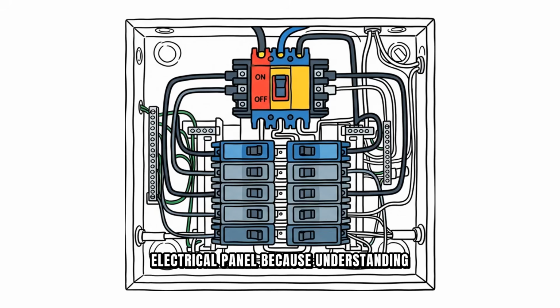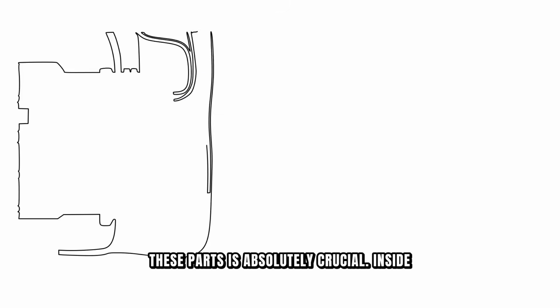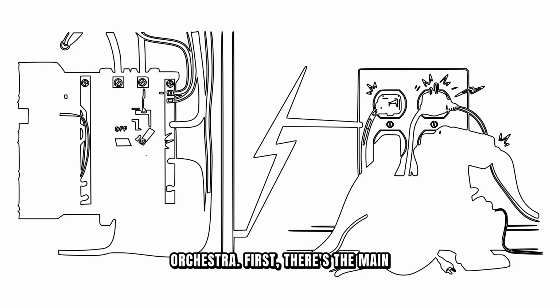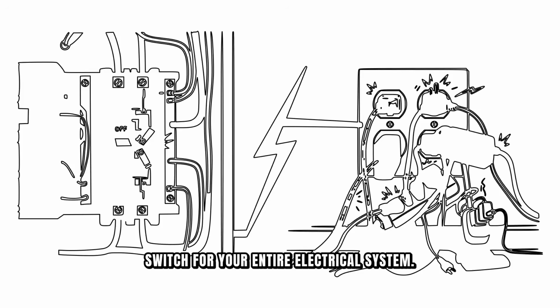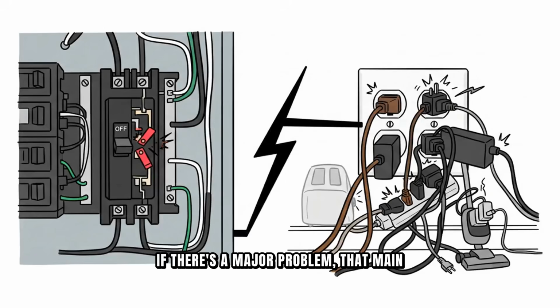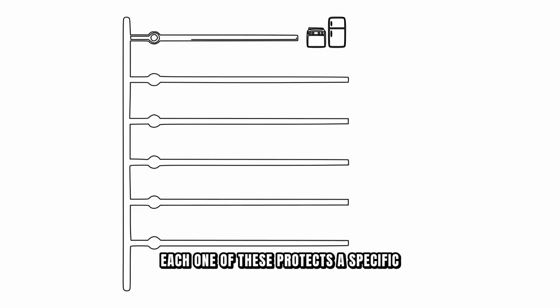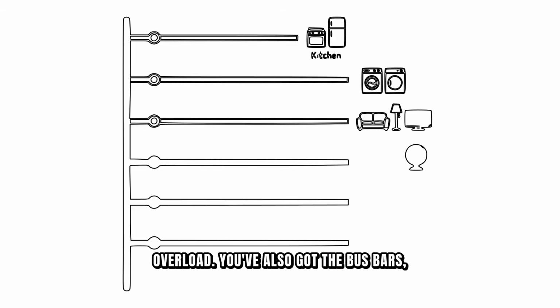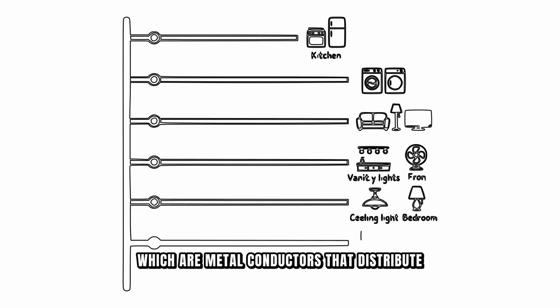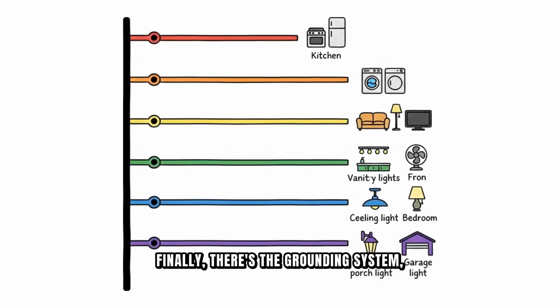Before we go deeper, let me explain the main components of an electrical panel, because understanding these parts is absolutely crucial. Inside your panel, you'll find several key elements working together like an orchestra. First, there's the main breaker, which is the on and off switch for your entire electrical system. If there's a major problem, that main breaker cuts off all power to your whole house. Then you've got all these individual circuit breakers, which are basically smaller switches that control individual circuits. Each one of these protects a specific part of your home from electrical overload. You've also got the bus bars, which are metal conductors that distribute electricity throughout the panel. And finally, there's the grounding system, which is absolutely essential for safety and helps protect you from electrical shocks.